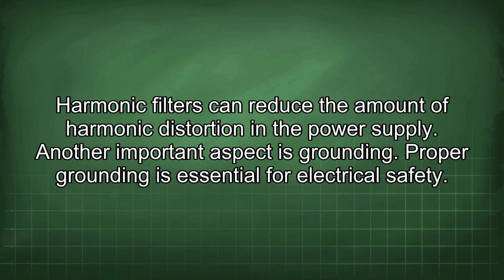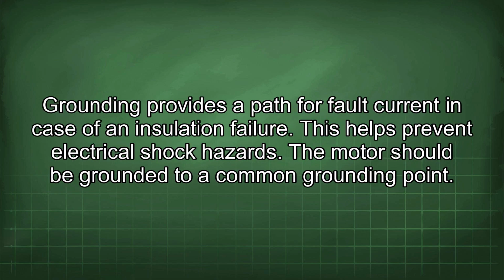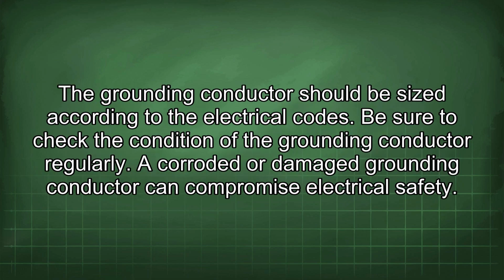Another important aspect is grounding. Proper grounding is essential for electrical safety. Grounding provides a path for fault current in case of an insulation failure. This helps prevent electrical shock hazards. The motor should be grounded to a common grounding point. The grounding conductor should be sized according to the electrical codes. Be sure to check the condition of the grounding conductor regularly. A corroded or damaged grounding conductor can compromise electrical safety.